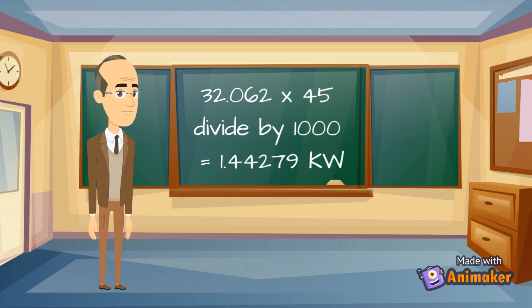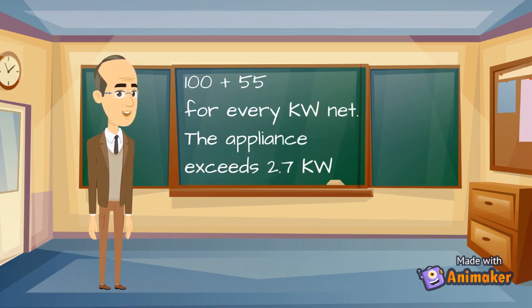If we divide by 1000, it tells us the maximum kilowatts for that room. Which is 1.44279 kilowatts, or rounded to 1.44 kilowatts. Our 1.44 kilowatts is the maximum size appliance for that room.